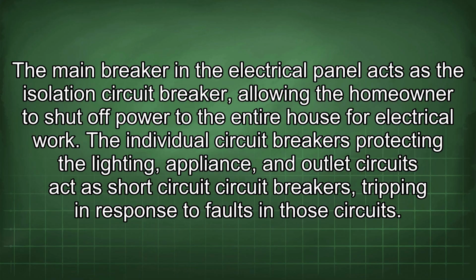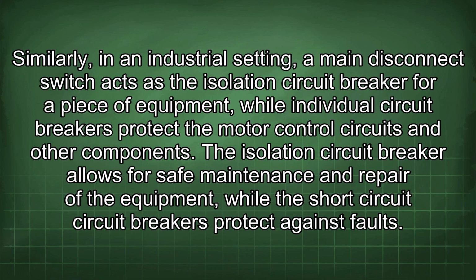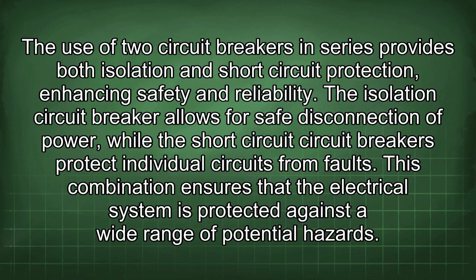Similarly, in an industrial setting, a main disconnect switch acts as the isolation circuit breaker for a piece of equipment, while individual circuit breakers protect the motor control circuits and other components. The isolation circuit breaker allows for safe maintenance and repair of the equipment, while the short-circuit circuit breakers protect against faults. The use of two circuit breakers in series provides both isolation and short-circuit protection, enhancing safety and reliability.